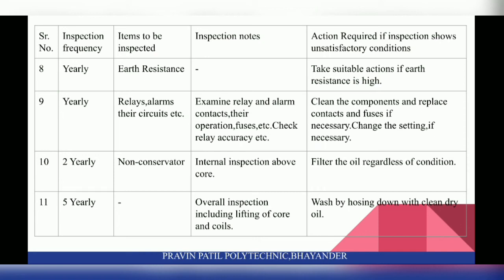On a yearly basis, also check relays, alarms and their circuits. Examine relay and alarm contacts, their operations, fuses etc. Check relay accuracy. Action required: Clean the components and replace contacts and fuses if necessary; change the setting if necessary.